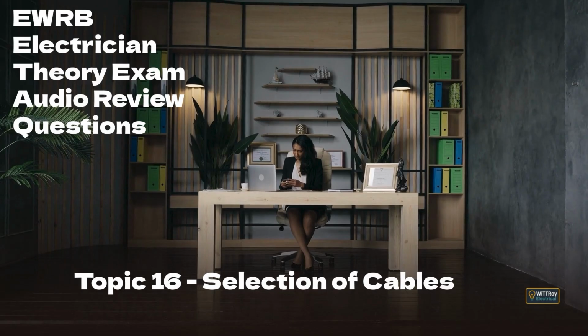Correct answer is option A. During a short circuit, current can be extremely high. Even for a short time, I²t heating can damage insulation or cause conductor deformation unless the cable can withstand it until the breaker or fuse operates.